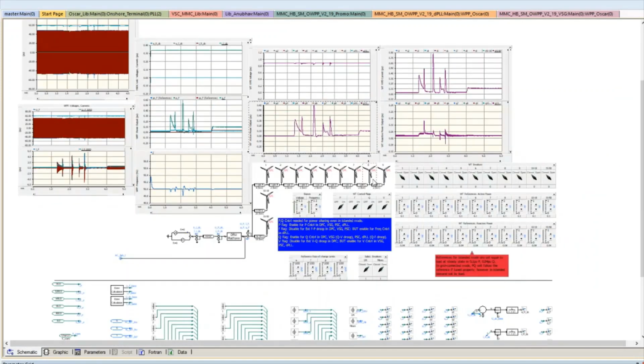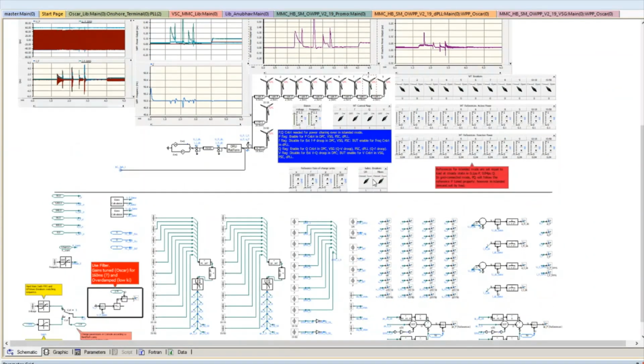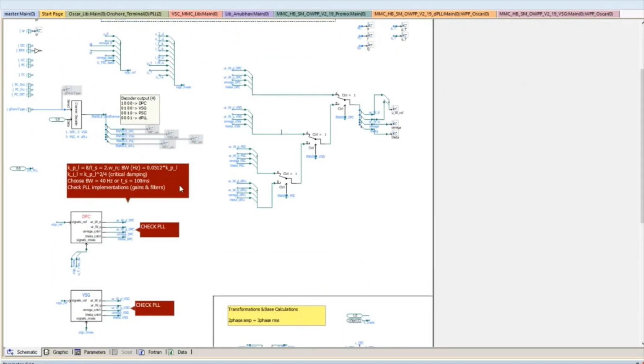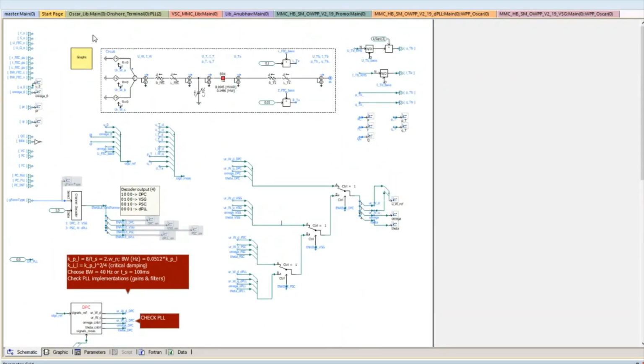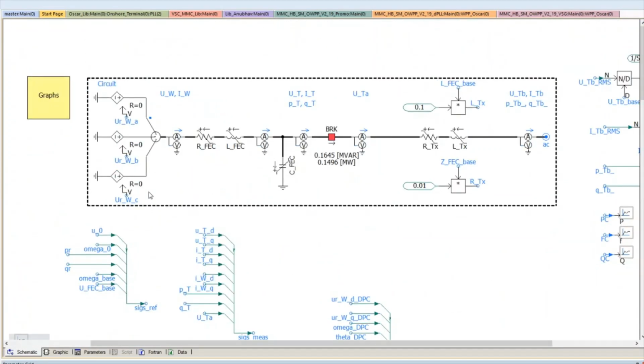Now, the wind turbine model in the wind power plant is the same for each turbine. It's an average model of the wind turbine grid side converter. So we just have a voltage source connected to the filter inductor and capacitor, and then the wind turbine transformer. And the wind turbine transformer is right now modeled just as a pure impedance, so there is no magnetic inrush and saturation, which is the focus of the next phase of this work.